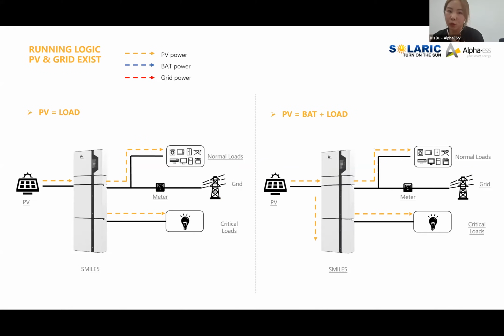When both PV and grid are available: if the load is less than PV, the PV will power the load, and any extra will go to charge the battery. If PV is not enough, the battery can kick in to help power the load together with it. If there's extra power after powering the load and charging the battery, you can choose to either feed the electricity to the grid, or curtail your PV generation to just meet demand.